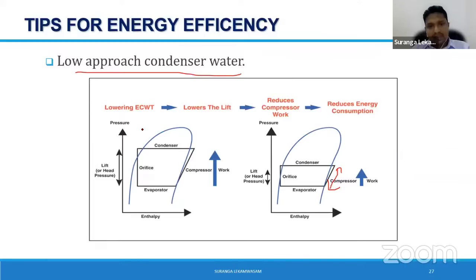But if you go for 30 and 35 condenser design, 30 minus 27 wet bulb is 3 degrees, which is the approach. But without any issue, you can select the cooling tower for 3 degrees or even 2.5 degrees. So with that understanding, we can go for 30-35.